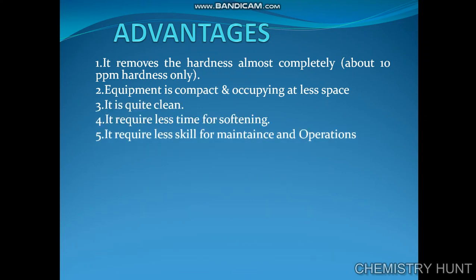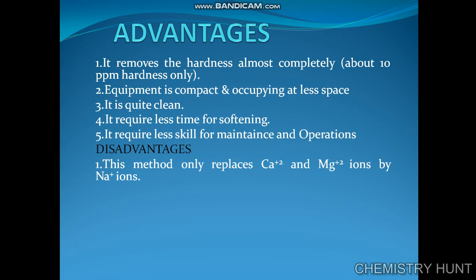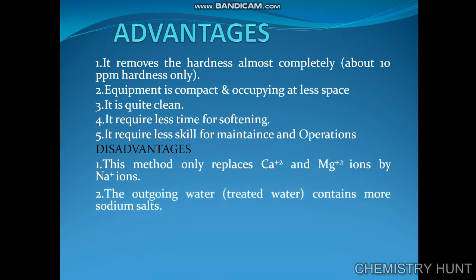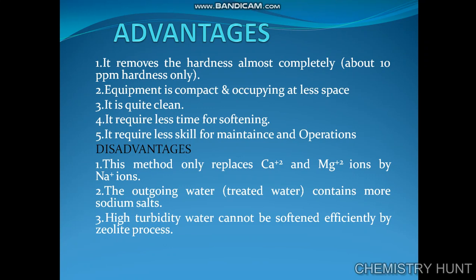Now we see the advantages and disadvantages. Advantages: it removes hardness almost completely; the equipment is compact and occupies less space; it is quite clean; it requires less time for softening; and it requires less maintenance and operation. Disadvantages: this method only replaces calcium and magnesium ions with sodium ions; the outgoing water contains more sodium salt; and high turbidity water cannot be softened efficiently by the zeolite process.